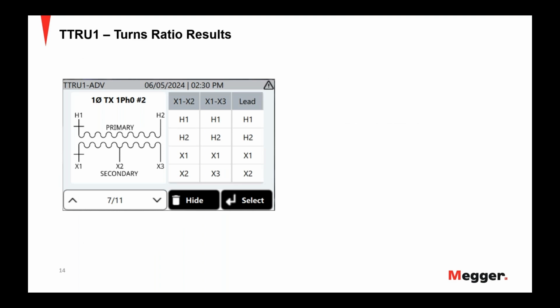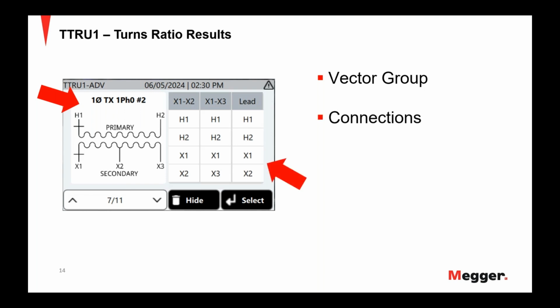Looking at the turns ratio setup, this is an example of one of the common single phase transformer vectors that we see on the market. And this is why we put that vector group directly on the instrument itself. So that way you can hold the turns ratiometer right next to the nameplate and say, yes, I'm confident that I have the correct vector group selected for the testing that I need to do. And then immediately next to that will be the connections for performing the test.